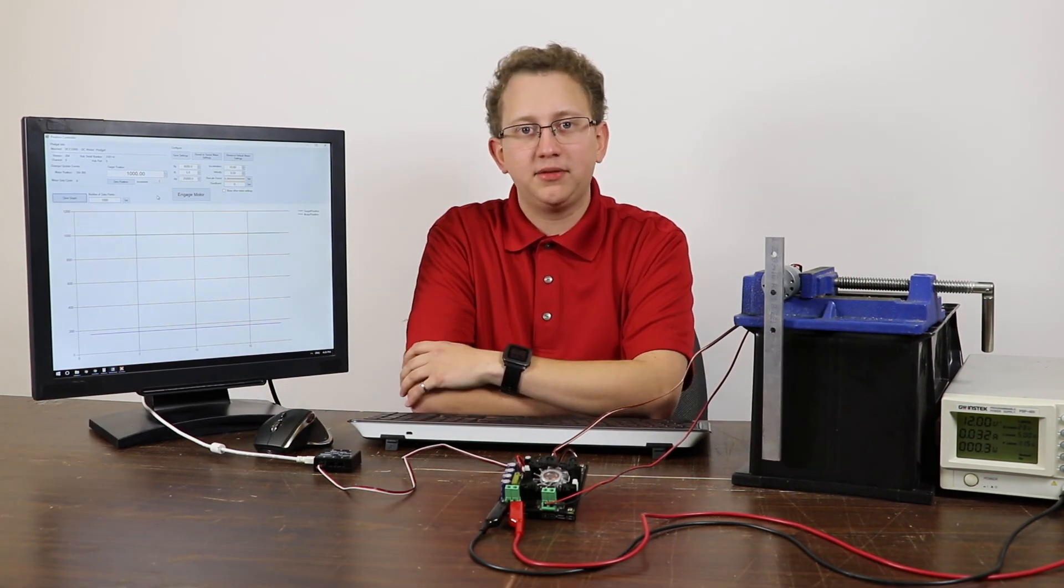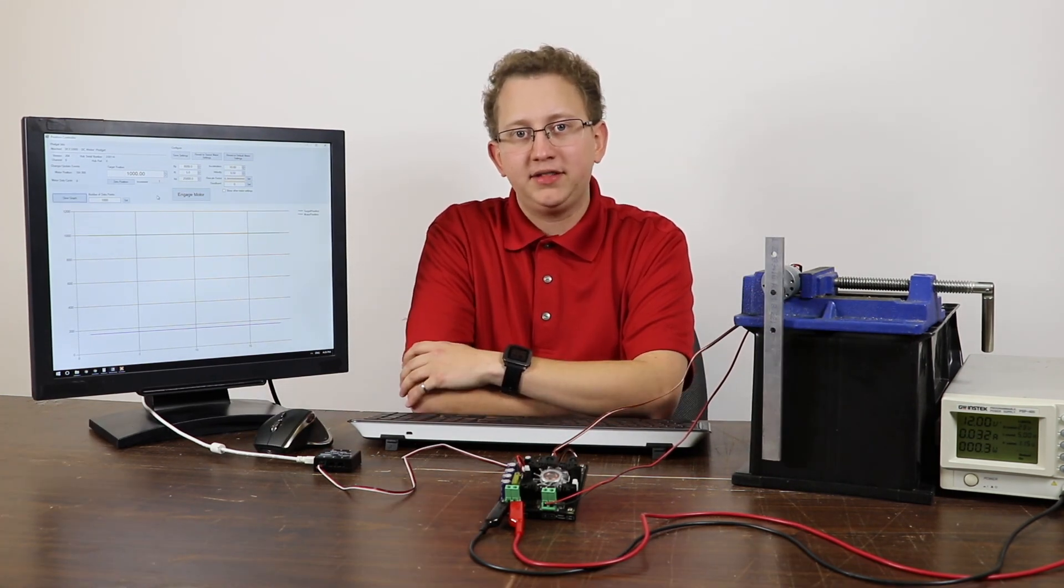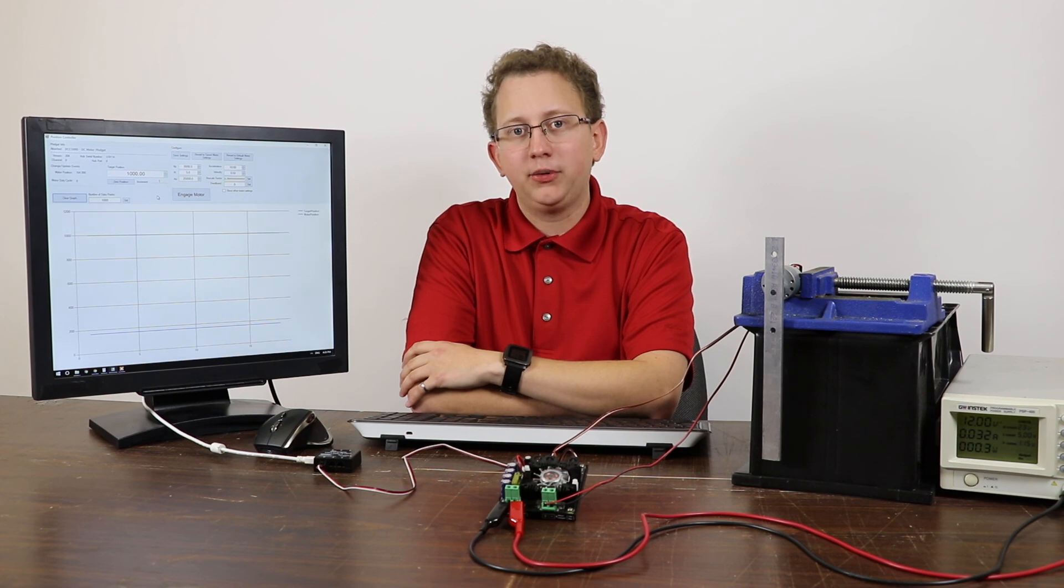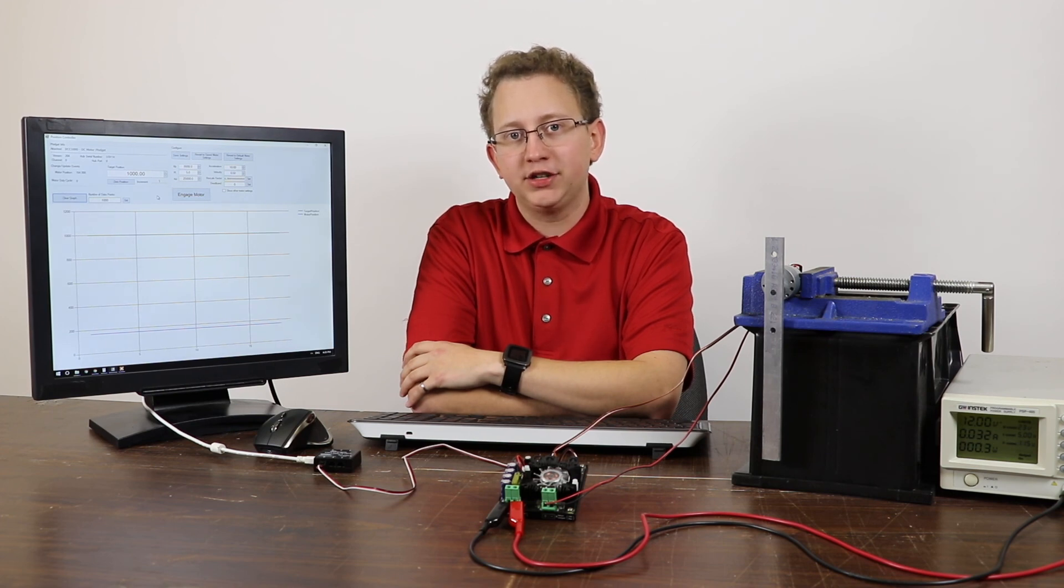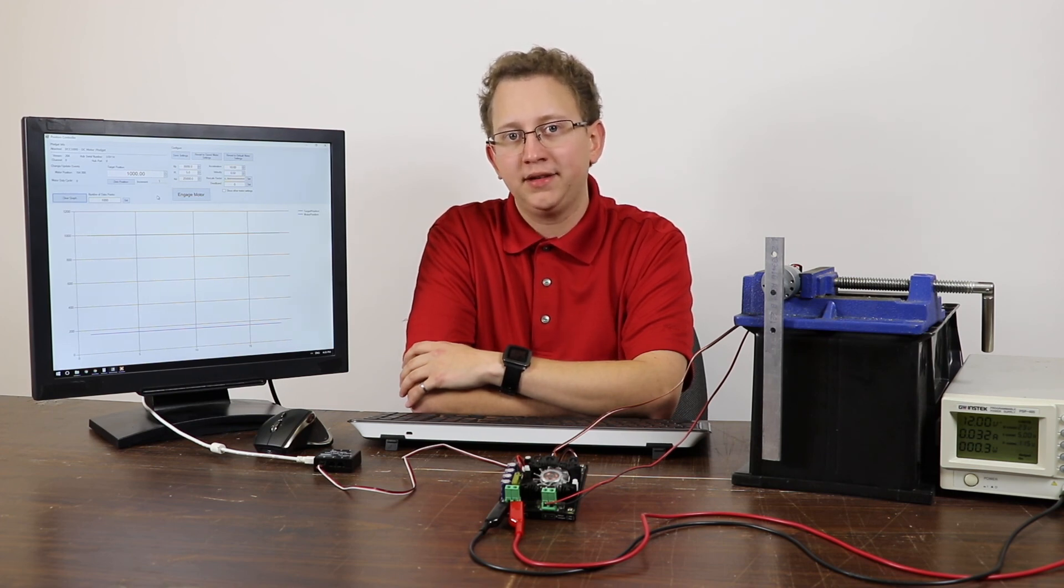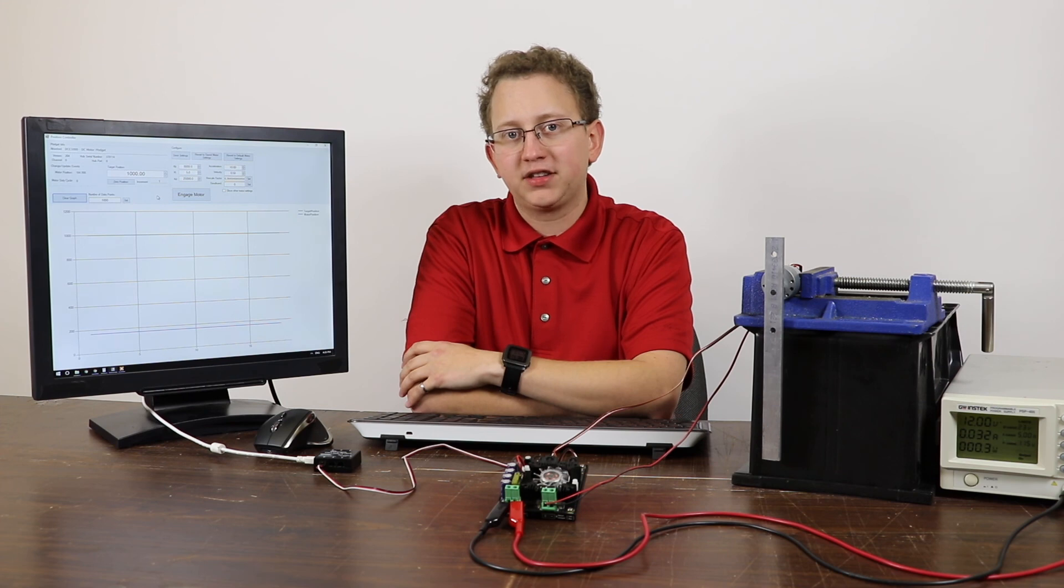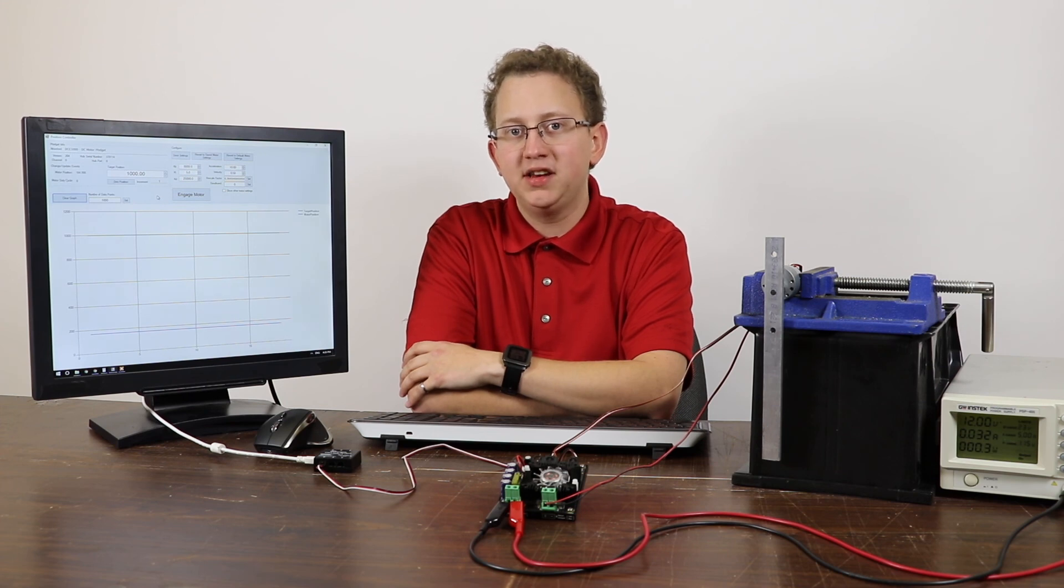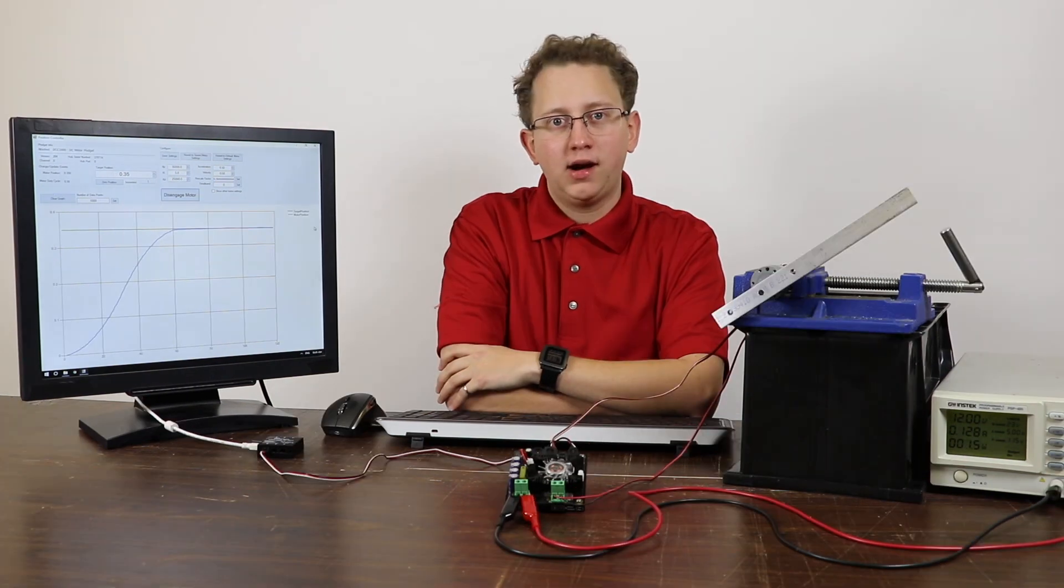Lastly, let's talk about deadband. Deadband refers to a region on either side of the target position in which control of the motor is relaxed. This prevents the controller from continually hunting for the target position.